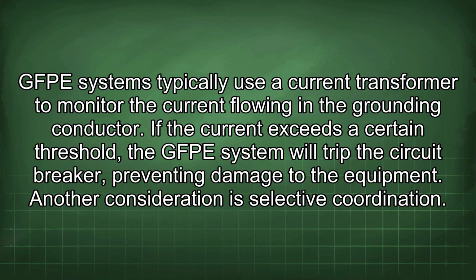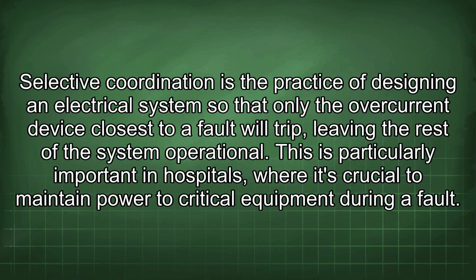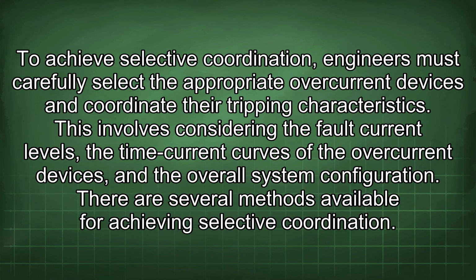Another consideration is selective coordination. Selective coordination is the practice of designing an electrical system so that only the overcurrent device closest to a fault will trip, leaving the rest of the system operational. This is particularly important in hospitals, where it's crucial to maintain power to critical equipment during a fault. To achieve selective coordination, engineers must carefully select the appropriate overcurrent devices and coordinate their tripping characteristics. This involves considering the fault current levels, the time current curves of the overcurrent devices, and the overall system configuration.